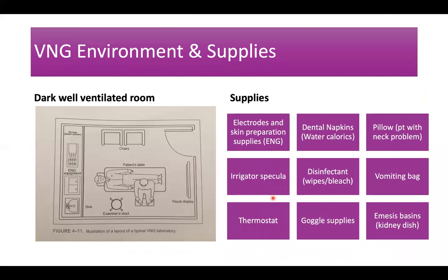The VNG environment is very important. The room should be isolated from the waiting area and away from the booth because calorics can be a difficult test and patients may react loudly. You don't need a very large room, but it needs to be very well darkened with proper ventilation and a thermostat. In very hot or very cold countries, getting the proper room temperature is essential so we can correctly control the irrigation temperature for caloric testing.